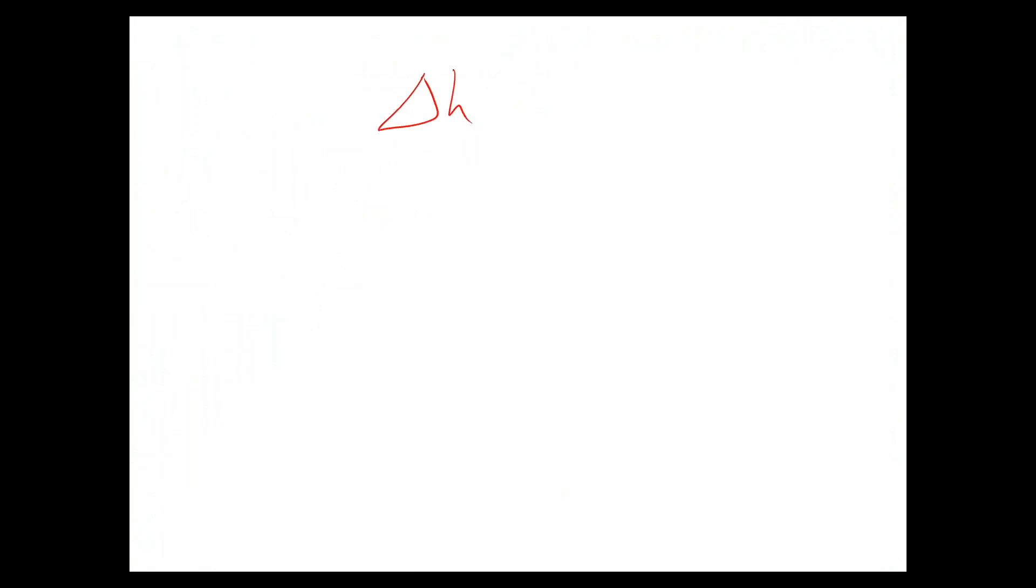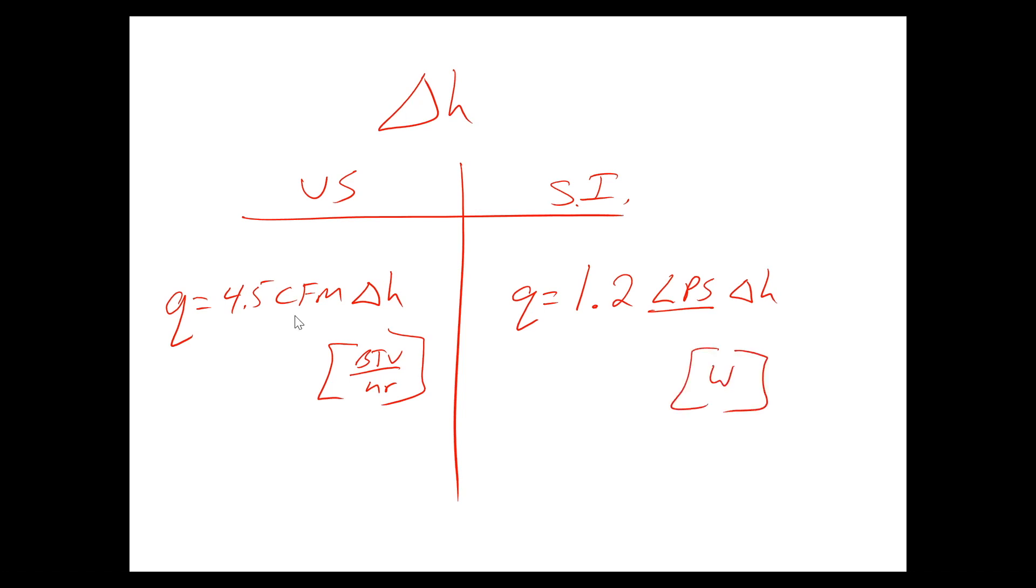And, in the U.S. system, the equation that we would plug that into is Q equals 4.5 times CFM times delta H. And, the units for this are going to be BTU per hour. This is somewhat of a shortcut equation. In the System International, the Q equation is slightly different. And, it's also a slightly different psych chart. But, all the mechanisms are the same. And, the equation for this is very similar. It's just different constants. For instance, this LPS means liters per second. And, the units for this are going to be watts, okay.